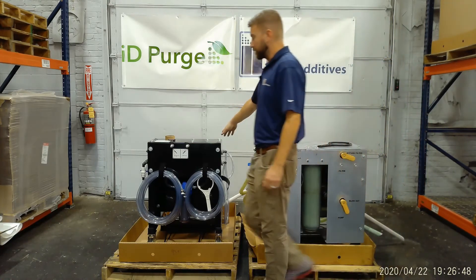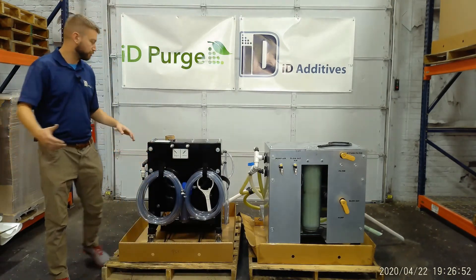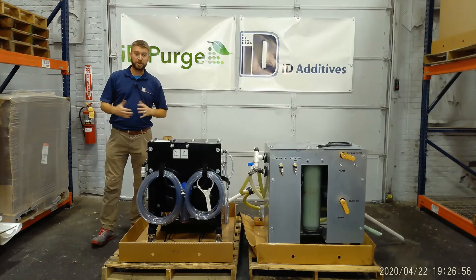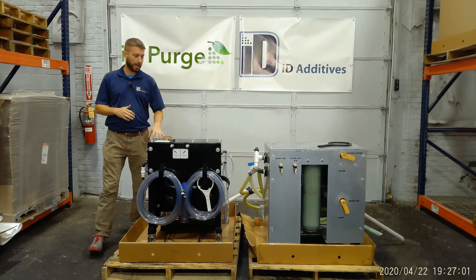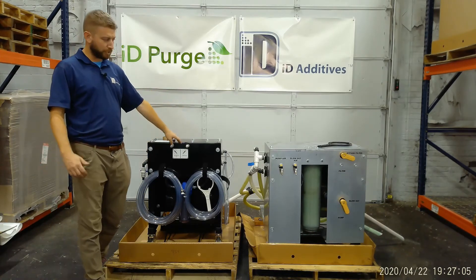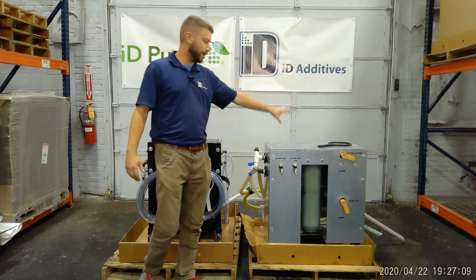The standard cart is applicable for probably 80% of the people out there — some of your smaller molds, some of your standard size molds, heat exchangers whether they're tube style or plate style. The standard cart will knock out a lot of that. It can operate up to 30 gallons of chemical, again at 13 and a half GPM.